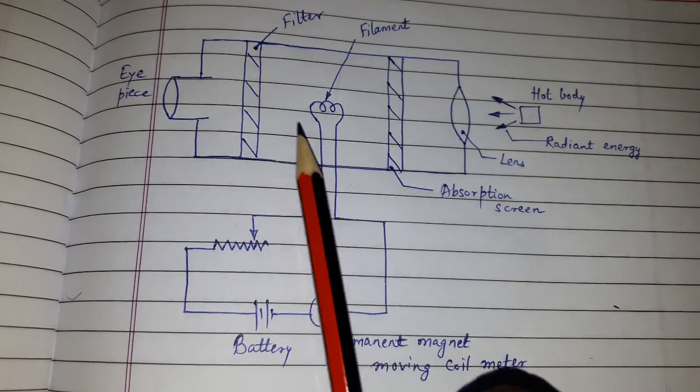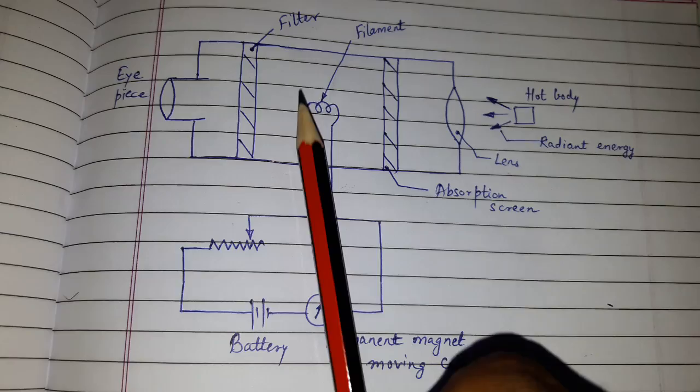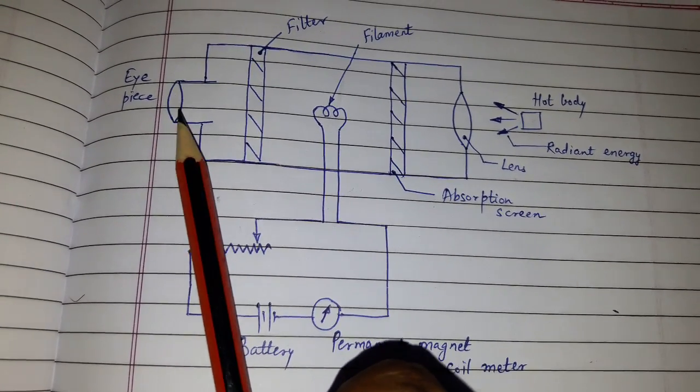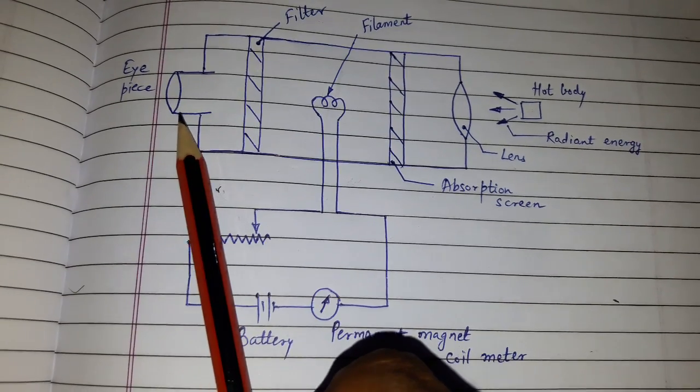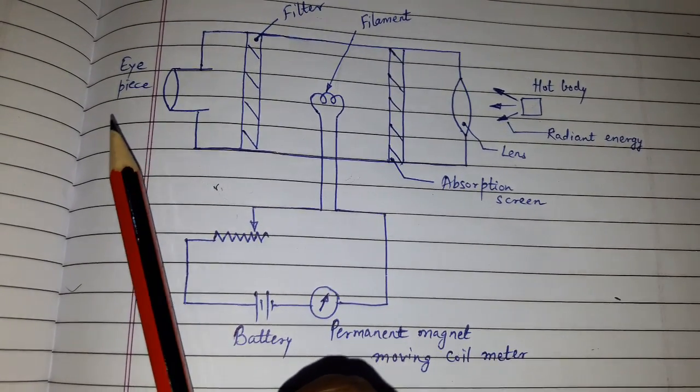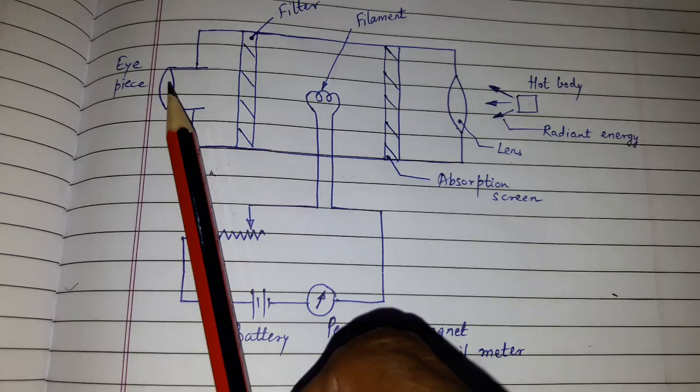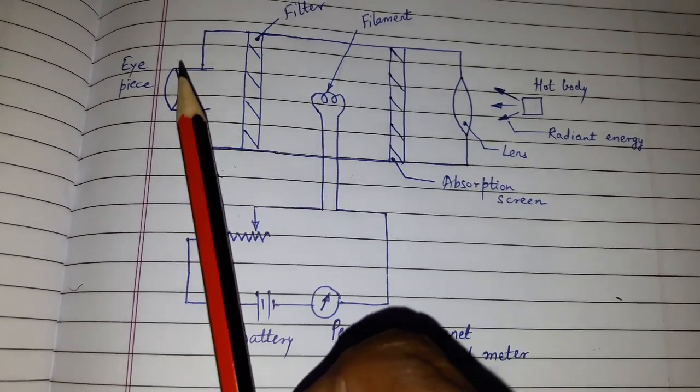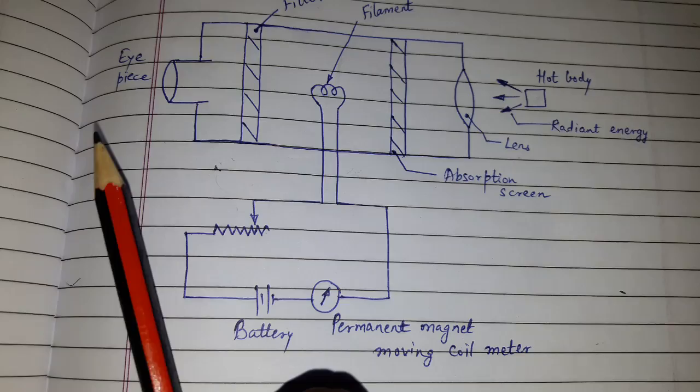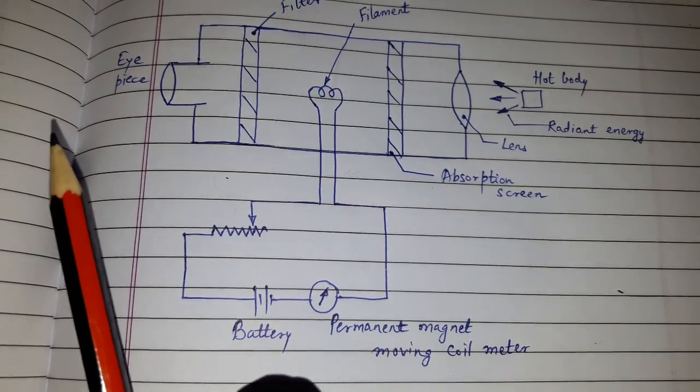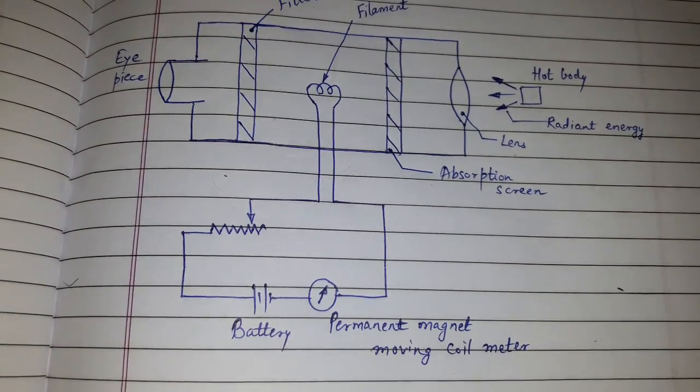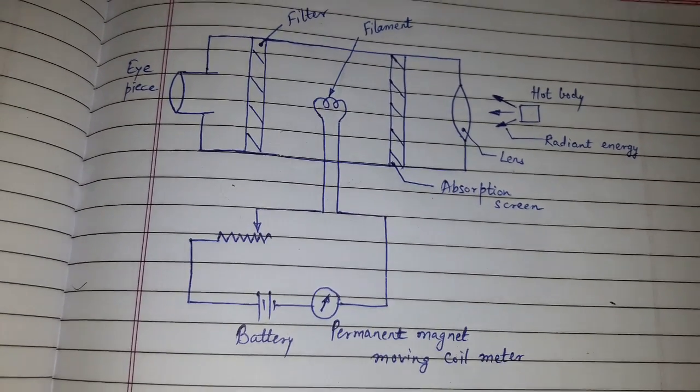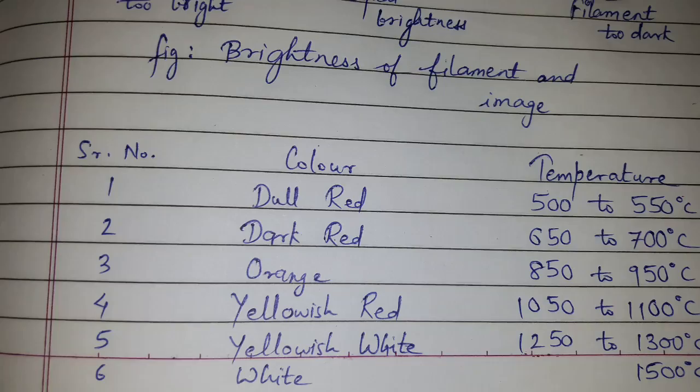So once you have frozen the brightness of the filament and image after both are equal, what you are doing is looking from the eyepiece. The wavelength of the radiation which is accepted is restricted by the color filter, and the brightness which you can see is compared with the standard lamp. And then you know what is the temperature, and this table will help you to know the temperature.